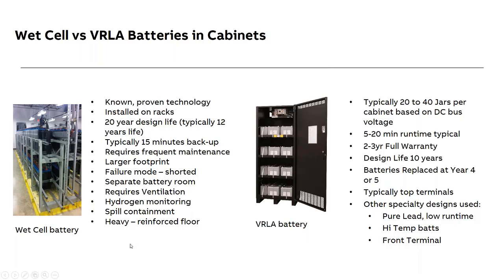Wet cell batteries have benefits. They live long. The failure mode, they usually fail shorted, which means if a cell fails, you don't lose a string, which you typically do in a VRLA battery. So some people really like wet cell batteries, but they require separate rooms. They require spill containment, eye wash stations, hydrogen monitoring, ventilation. And you need somebody to run around and top up the water. So the market has almost entirely moved away from this.